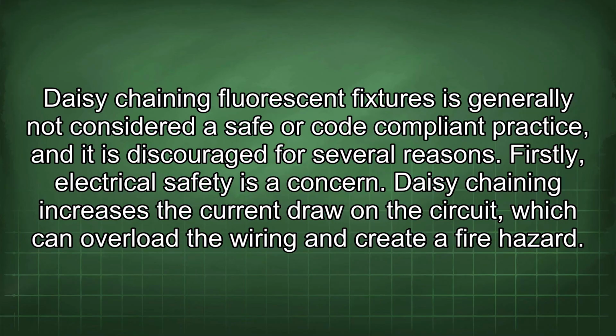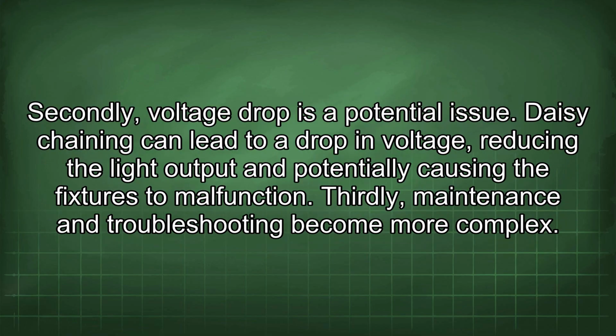Daisy chaining fluorescent fixtures is generally not considered a safe or code-compliant practice, and it is discouraged for several reasons. Firstly, electrical safety is a concern. Daisy chaining increases the current draw on the circuit, which can overload the wiring and create a fire hazard. Secondly, voltage drop is a potential issue. Daisy chaining can lead to a drop in voltage, reducing the light output and potentially causing the fixtures to malfunction.